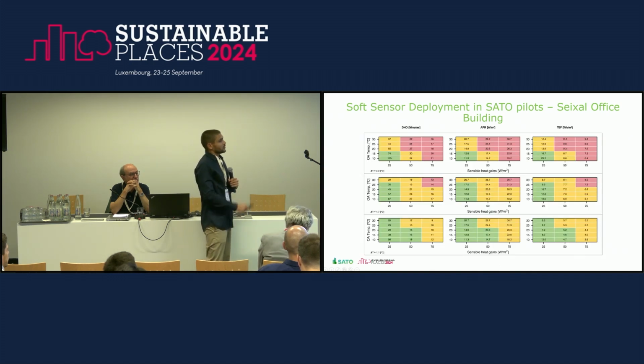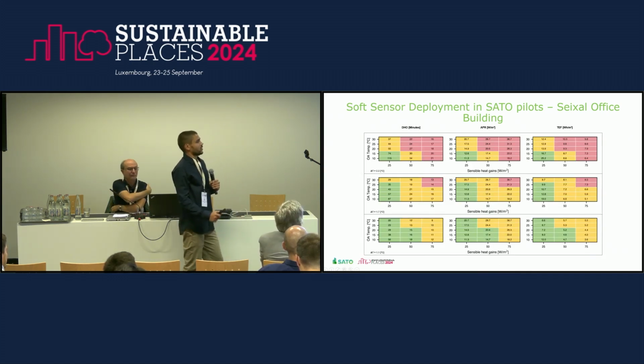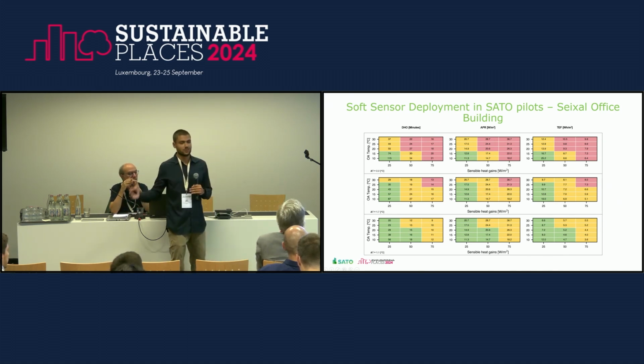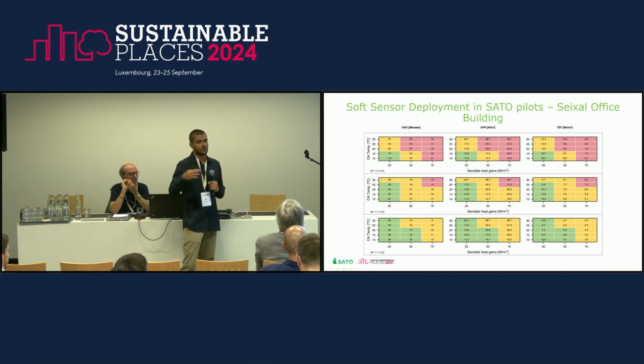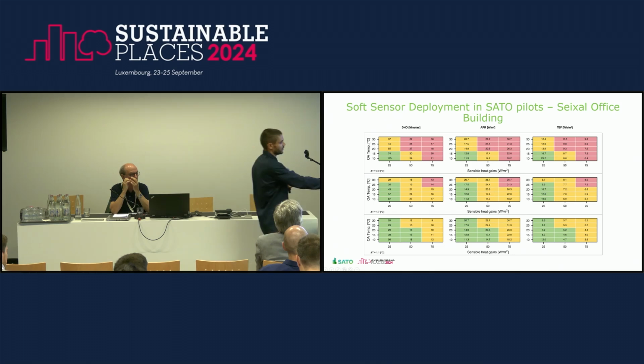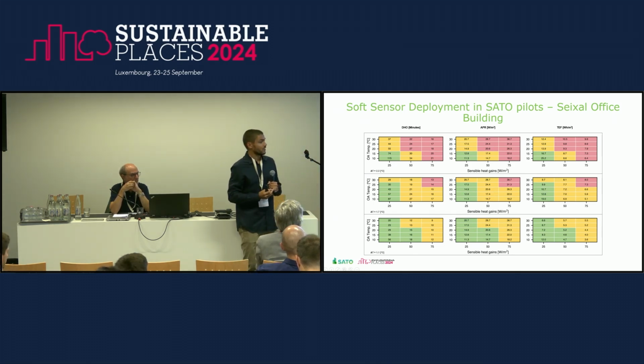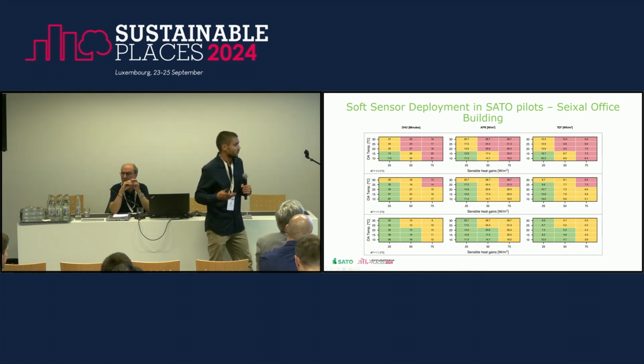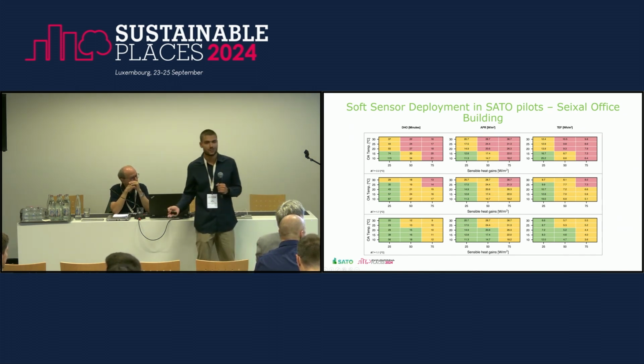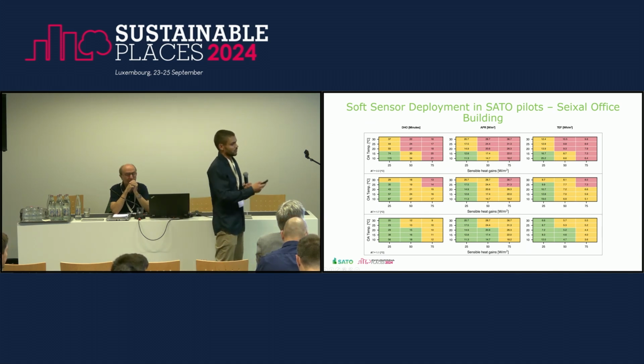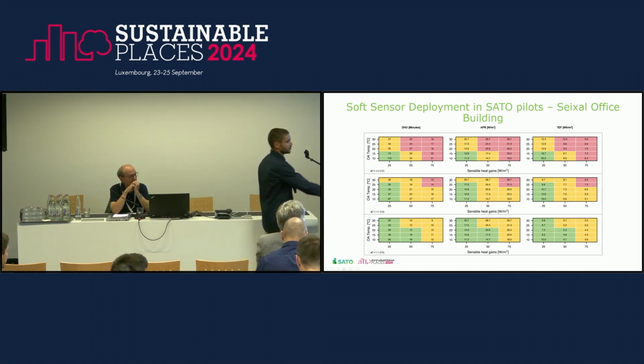And when we deployed, we calculated the duration for different scenarios, like 25 watts per square meter, 50 watts per square meter, and 75 watts per square meter. These numbers include internal heat gains and solar gains. We did a review of typical internal gains in office buildings, and we found that the usual number is between 25 and 50 watts per square meter.